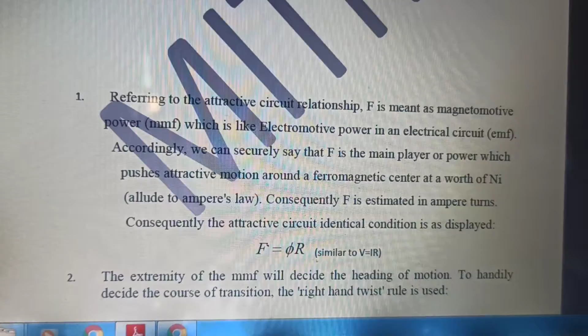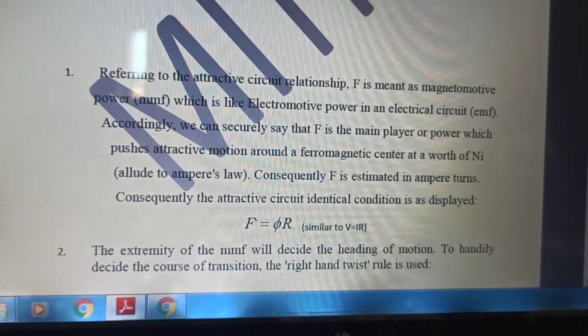Now for the same flux to flow, obviously we will need a larger magnetizing current. Is it clear or not? That's why if you look at the machines, in the machine there is an air gap, whereas in a transformer, the core is there to connect the two windings. Therefore the magnetizing current required to set up the flux will be higher in a machine as compared to a transformer. Okay, next.